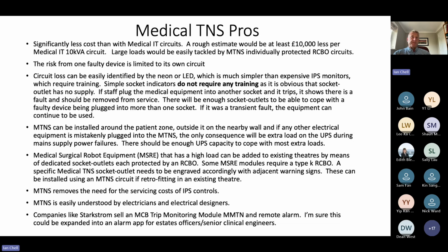If you get a circuit trip, and staff plug the medical equipment into another socket and it trips, it shows there's a fault and it should be removed from the service, okay? And there should be enough socket outlets to be able to cope with a faulty device being plugged into more than one socket.